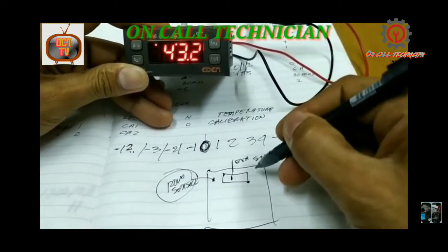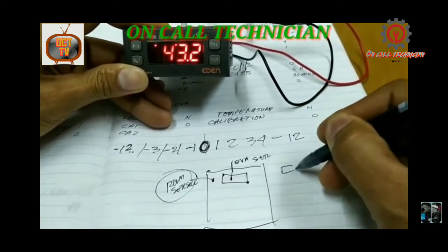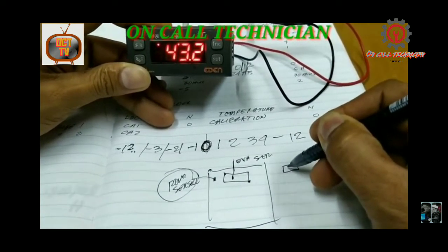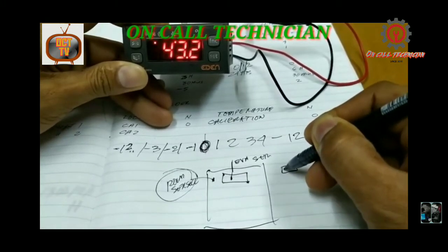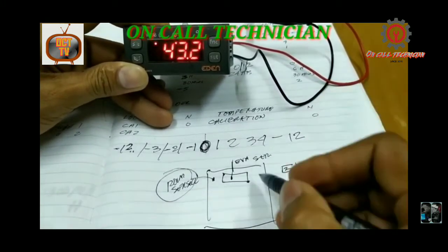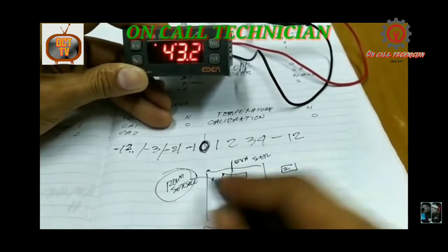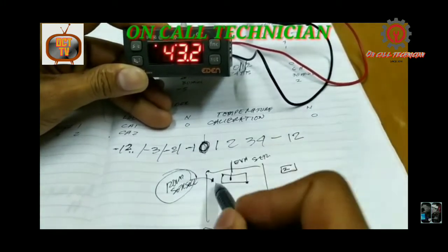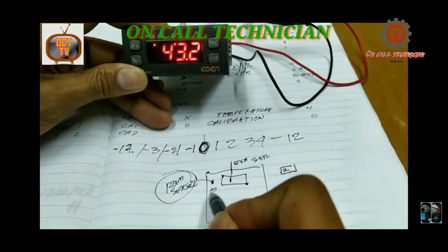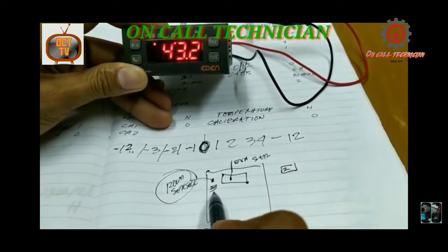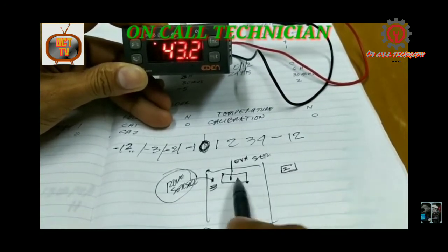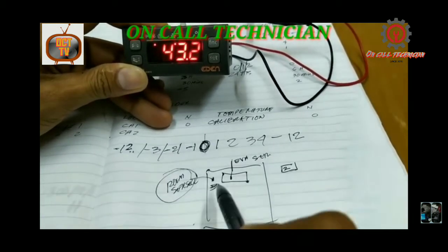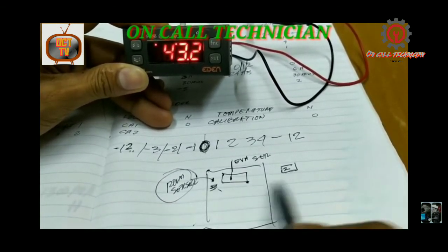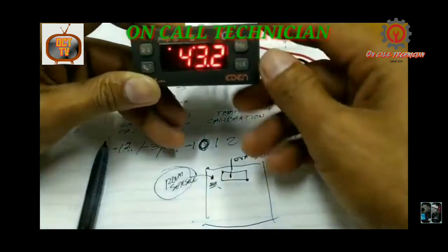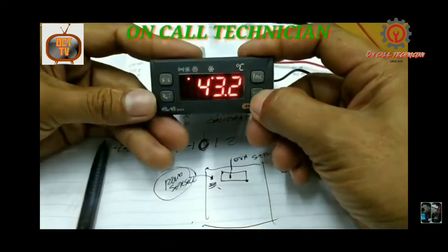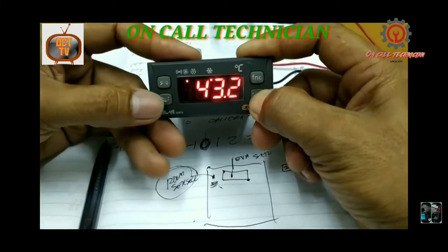For example, I'm going to draw out our digital control. For example, the display for the digital control is positive 2, and it reads this sensor. This is the room. For example, it reads positive 5 in the cabinet, so we have a differential of 3. So we need to adjust that one. That is the purpose of the calibration.